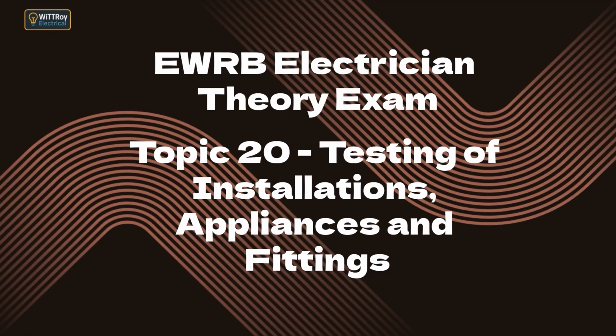Today we are learning topic 20, testing of installations, appliances, and fittings, which is one of the key responsibilities of a licensed electrician. Every installation must be tested in a safe, logical, and methodical way before it is connected to supply. Testing is not optional. It is required by AS/NZS 3000, AS/NZS 3017, and the Electricity Safety Regulations.